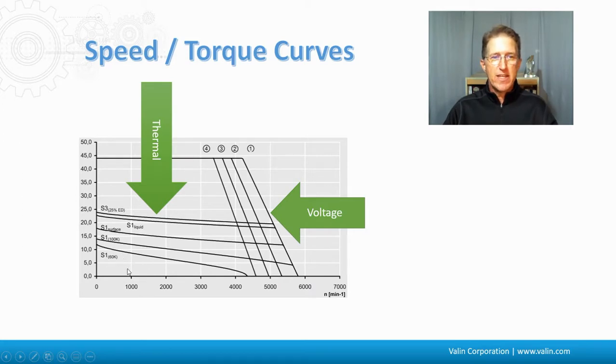And this particular curve looks at the different rise in temperature and the different heat sinks and the different assumptions that are made. So this one right here, this assumption, is a pretty limited continuous duty cycle, whereas you get a longer, bigger duty cycle up here. But then above this one, it's all peak. So we really have to keep in mind what the application is of the motor. If the motor is in a box where there's no airflow at all, it's not going to get nearly as much heat dissipation as one that is out in the open with a fan blowing air across it.